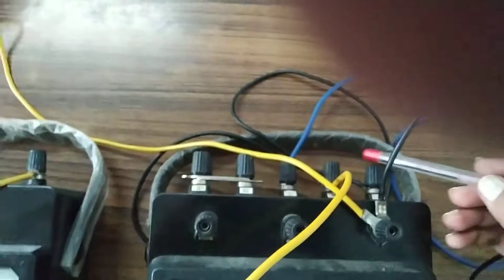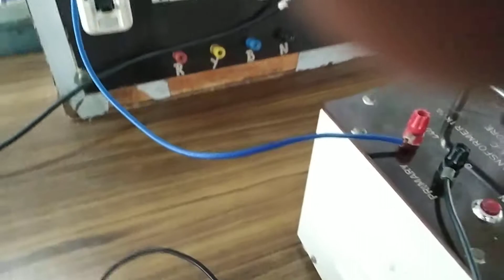Again, in the ammeter, we know that the range is 0 to 5 amps. From the 5 amps terminal, a connection is taken and given to the M terminal of the wattmeter. Again, M and C should be short circuited with the help of a wire. From the L terminal, a connection is taken and given to the phase of the high voltage side. That is the 440 volt side, right?